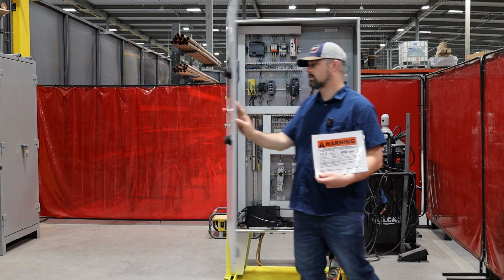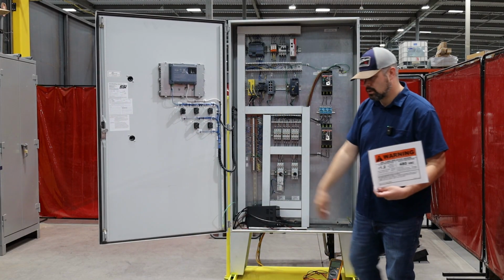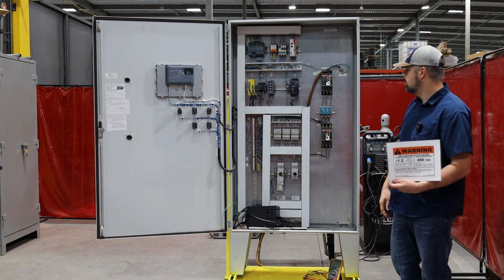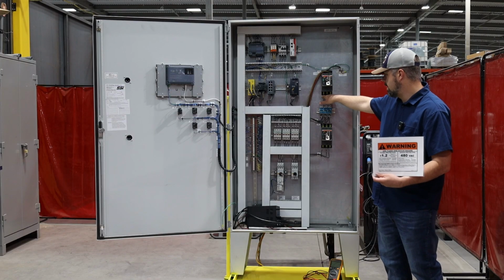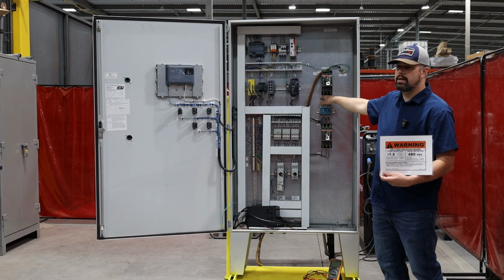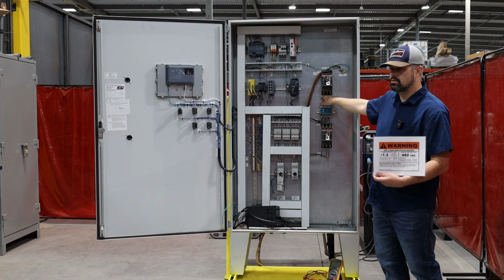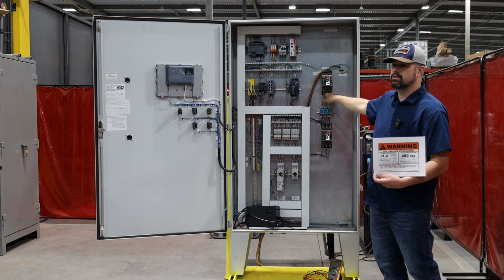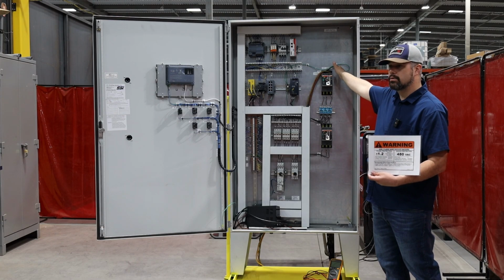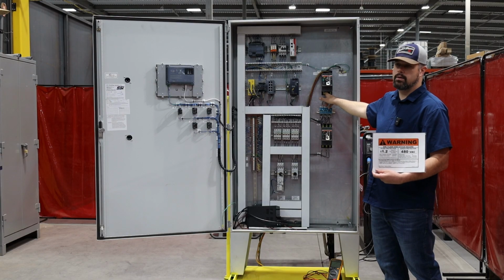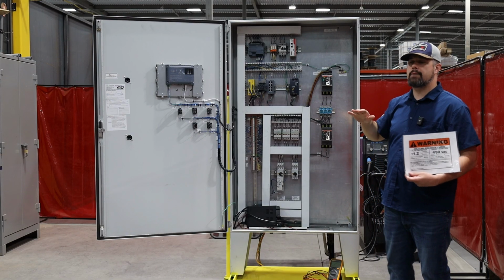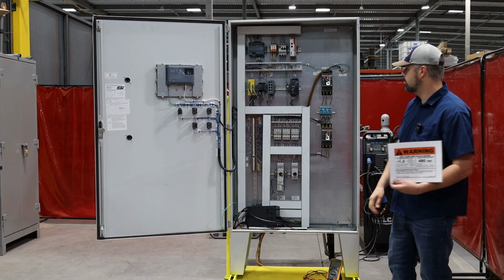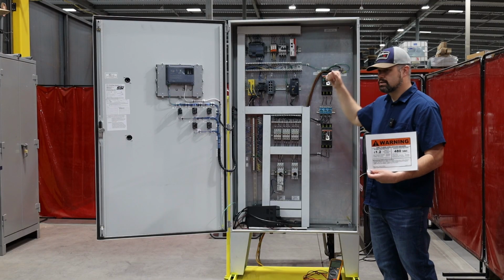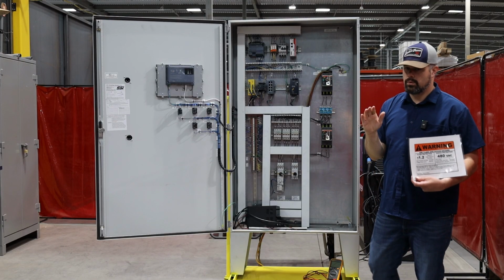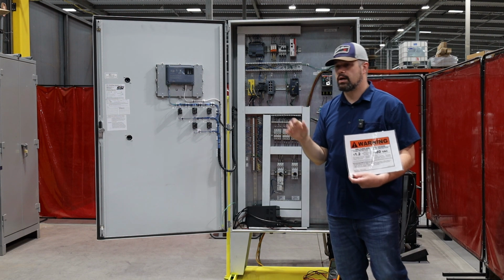And so what that looks like, you open the cabinet, and like we walked through the scenario earlier in the classroom, on the downstream side of the main disconnect, you do your verification, right? Phase to phase, phase to phase, phase to phase, then black lead to ground, and red here, here, and here, just to verify complete absence of voltage. You should get 0 volts on all of them.